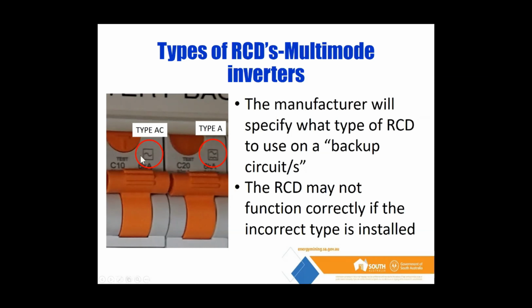You can see here two RCBOs that look exactly the same, but if you look a little bit closer, we've got a different type of diagram here. What this one is telling me is this one can handle a little bit of DC injection, which is possible across a transformerless multimode inverter. Now if we're getting DC in an RCBO of a type AC RCD, there's a big possibility that this might flood the coil and inhibit its operation. So it's pretty important to know what type of RCD to install on your output.